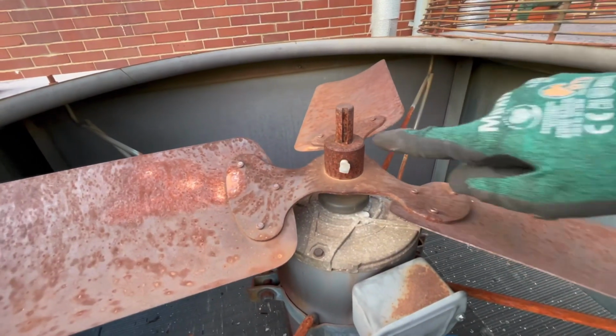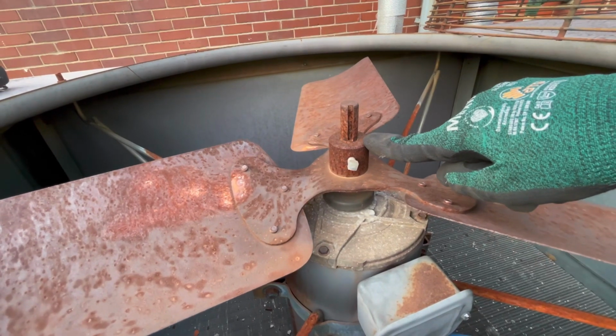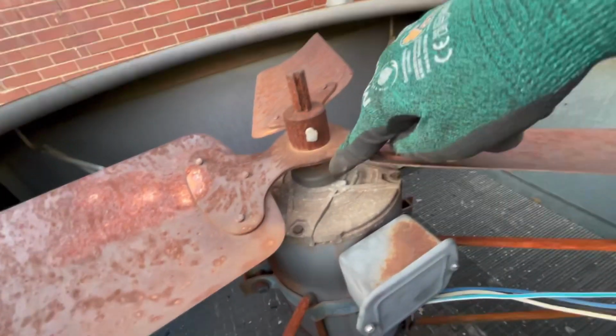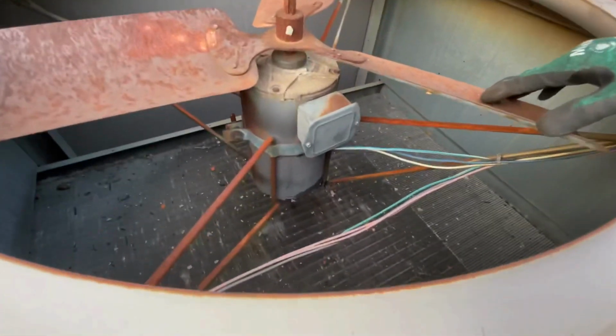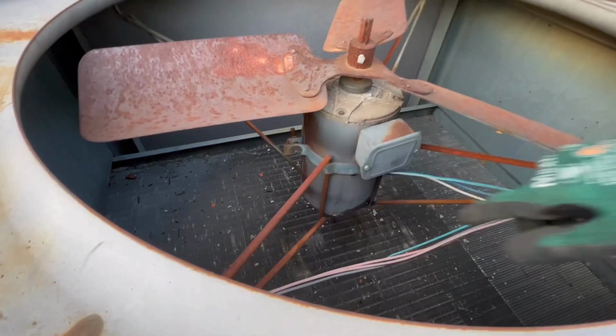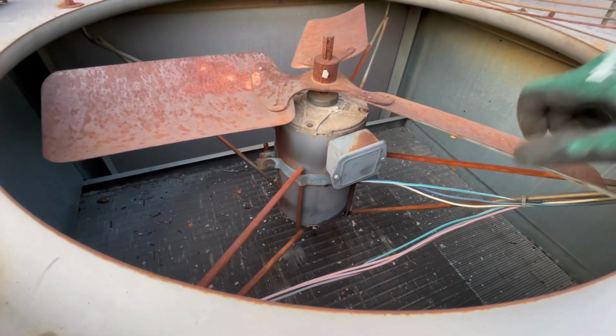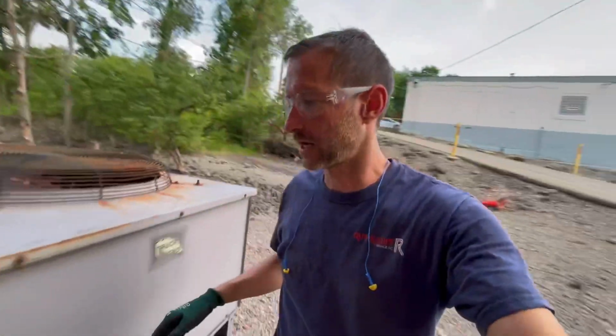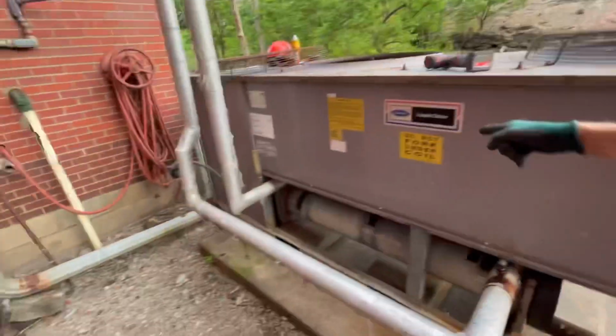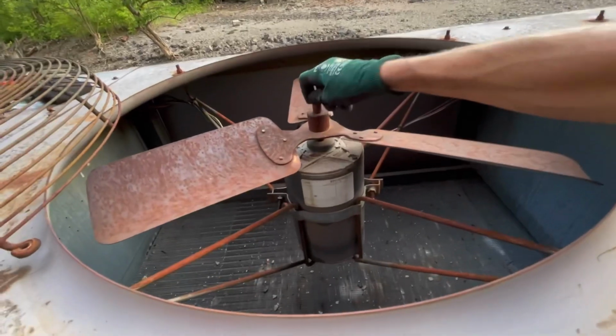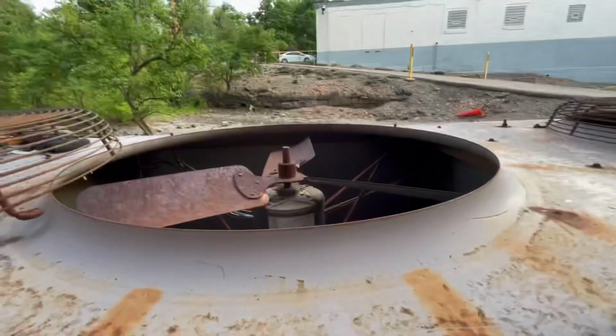You see this blade? I don't care how much heat and PB Blaster you put on this, don't do it. Replace the blade. A lot of times the rain shield comes with them. It's a 3-phase motor, so there is no capacitor. But I'm going to check this out and spray it down with some PB Blaster on the bolts to take this off. I'm going to gather this motor's model and serial number information and call Carrier tomorrow morning, everybody. So, okay guys. That's what it is, bad bearings, just wear and tear.